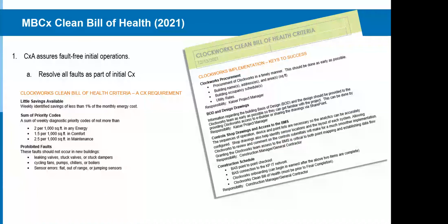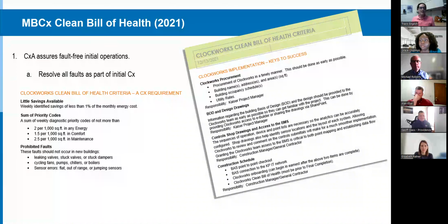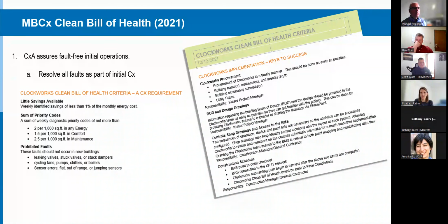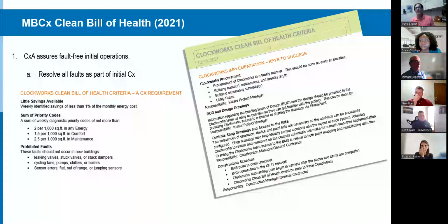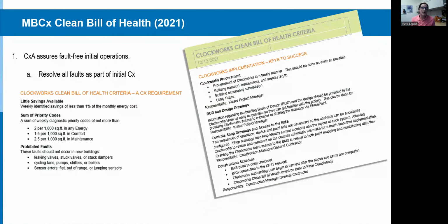We also have, for our new projects, a monitoring-based commissioning program, a fault detection program called Clockworks. That's another national contract we have. We have what we call the clean bill of health. The basic idea is that if you buy a new car and drive it off the lot, the engine lights shouldn't be on. So if you buy a new building that's brand new with a brand new control system, everything should be working and functioning correctly. This is a way to measure that with the clean bill of health. There are 3 types of faults: energy faults, comfort faults, and maintenance faults. We've set up so there can only be a certain number of faults per 1,000 square feet within that system, since it's a brand new building. It should be running great.